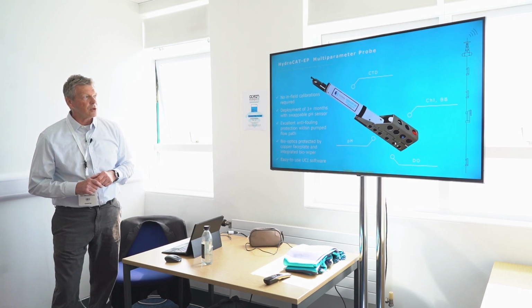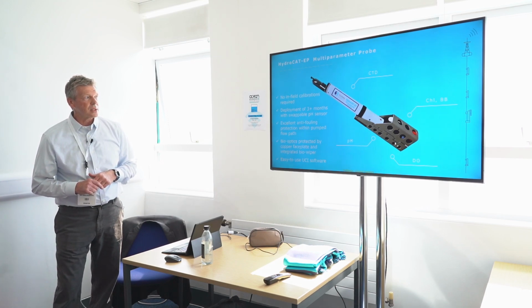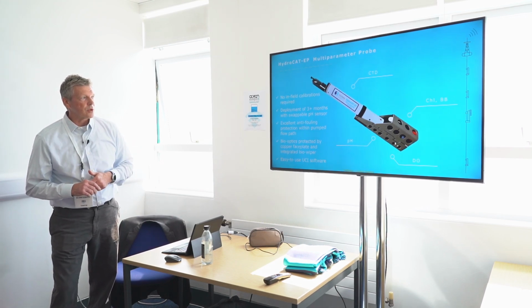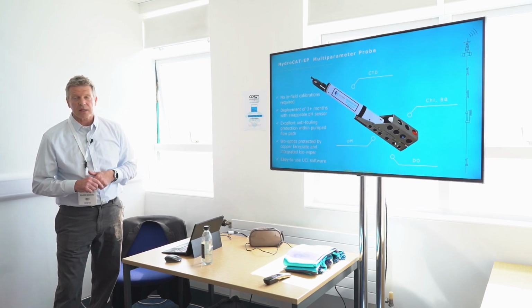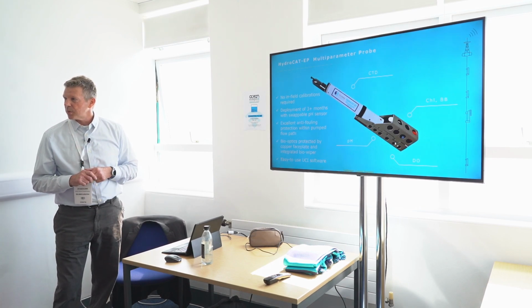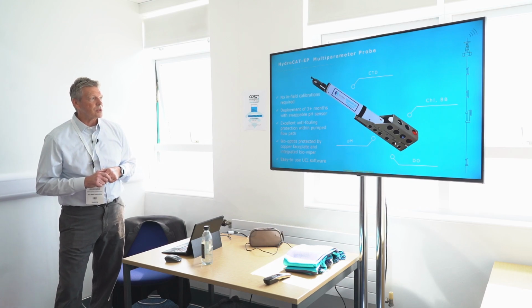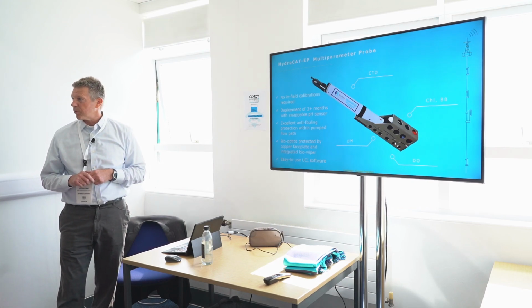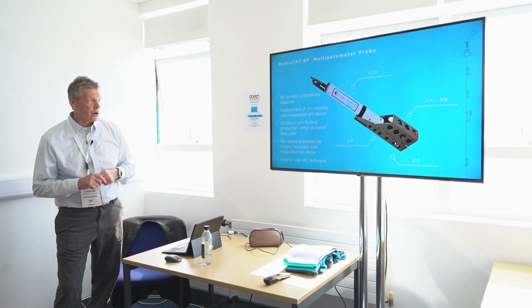It has the advantage that you don't really require field calibrations. You can achieve deployment times of over 3 months by swapping out the glass ball pH module. You also have the ability to do field calibrations, 3-point calibrations of the sensor, if you so desire.